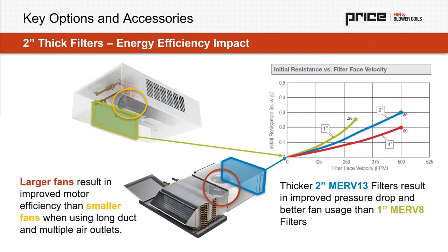The byproduct of that is lower pressure drop, which means you could have longer duct runs or a higher supply air volume. But most importantly, there are two different realities: an improvement in IAQ with the use of a MERV 13 instead of a MERV 8, which could be a value to owners, and a much happier fan with much lower acoustics and lower power consumption. So when we look at trying to reduce energy consumption, the thicker the filter, probably the better the solution.